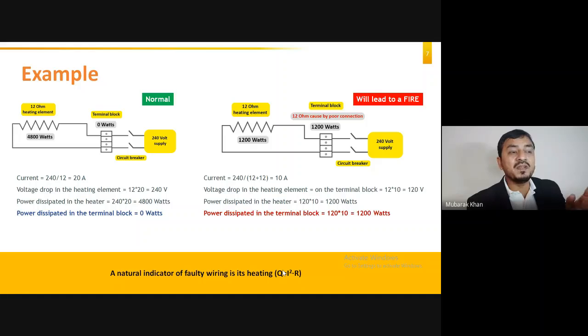Now, what will happen if the same 1200 watts of energy is dissipated on the terminal block? It is not designed to withstand that much energy. The terminals are very weak, very small, so they cannot withstand that much energy. So it will start to heat. The energy will get dissipated in the form of heat. Now there is a very small amount of copper, so it will not be able to withstand that much heat, and eventually either that immense heat will cause a fire if there is fuel in the close vicinity, or the contact will burn, right?